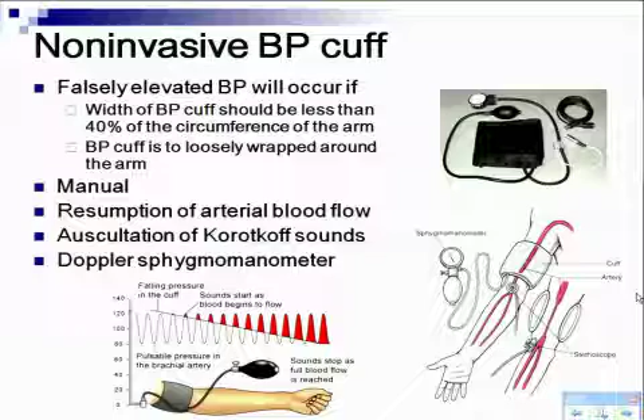What it basically does is it doesn't listen, but it feels pulsations. When you squeeze the arm completely, the pulsations will stop. So this is oscillometric cuffs. What you're hearing right here is you're listening. But let's see, yeah, this one. This is what I was talking about. The automated blood pressure cuff will actually sense when your arterial pulse comes back. The cuff will inflate and go up and down. This is called the oscillation measurement. And when it hits the peak oscillation, it usually takes 3 pressures like that at the peak, and it calls that the mean.